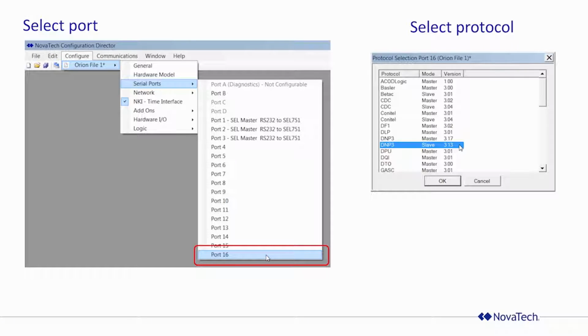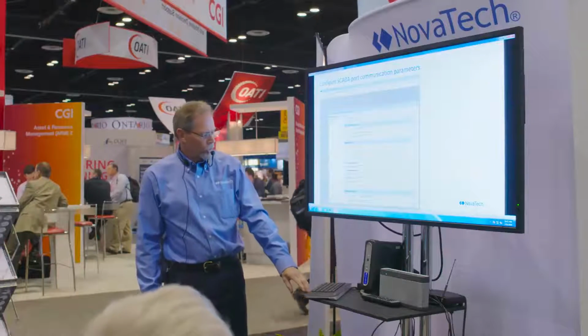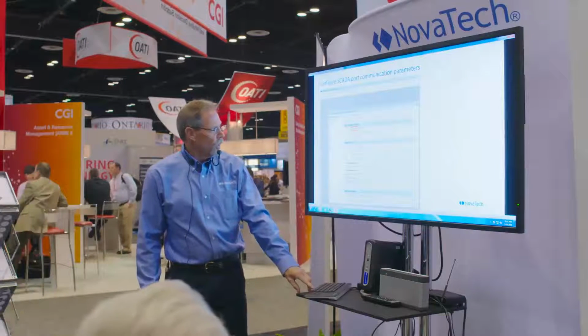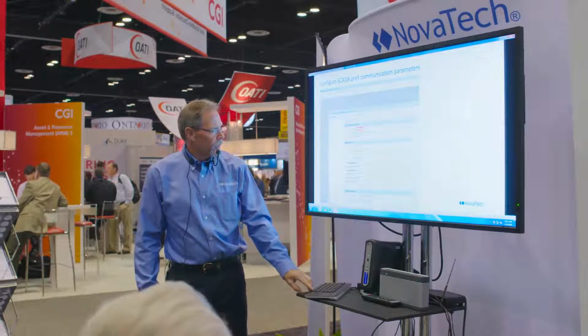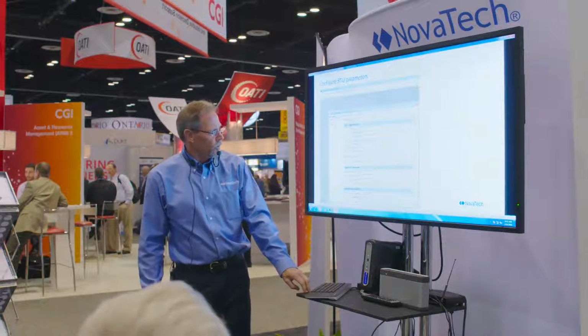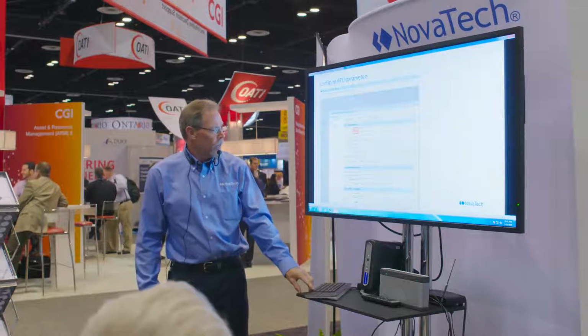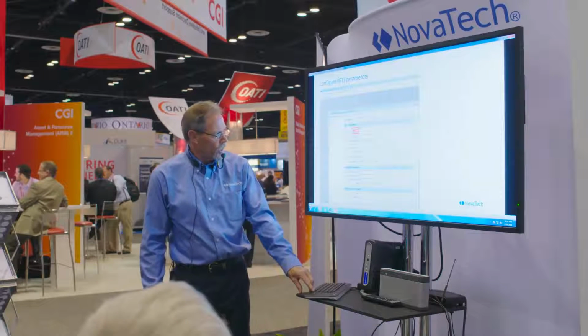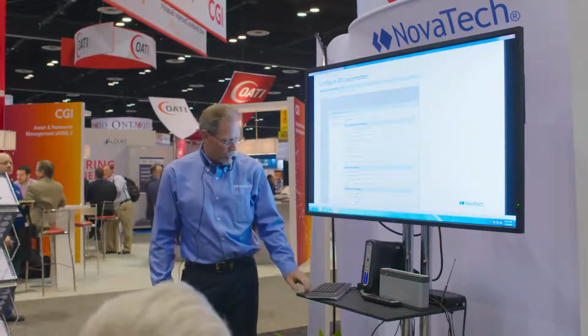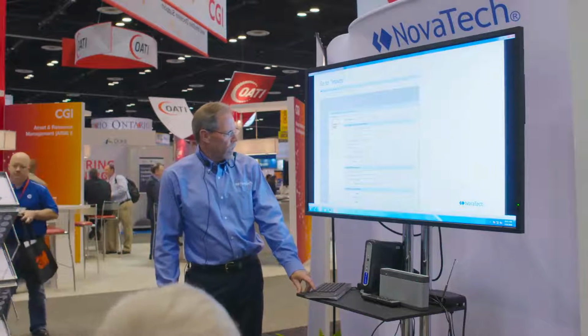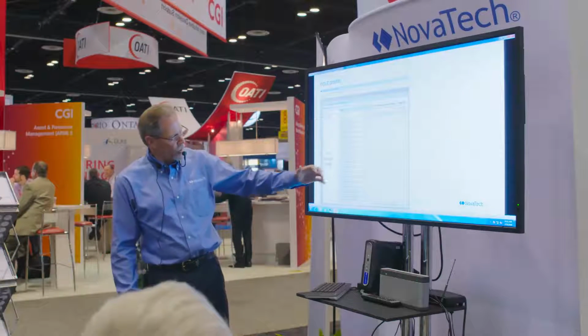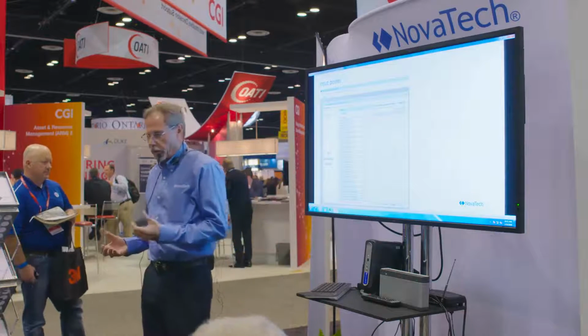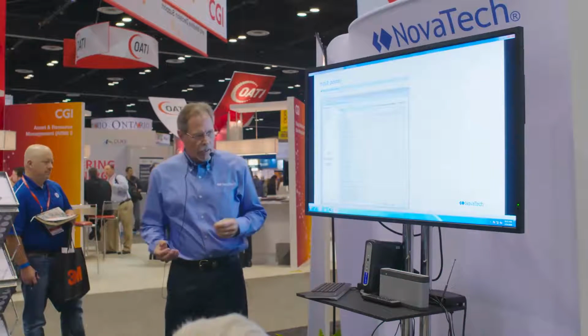I'm going to go in and select my slave protocol. So the Orion is a master to the IEDs that it's connected to. It's a slave to the SCADA master that wants to pull data from it. So I'm going to pull up my DNP3 slave option, assign a unique port name, add an RTU. From here I want to give it a specific substation name, whatever the device address is that SCADA has told me to assign to it. Once I've done that, I simply go down and click on the inputs. So now I have all of the data available here that I've configured from those 4 IEDs that I want to bring data back into.